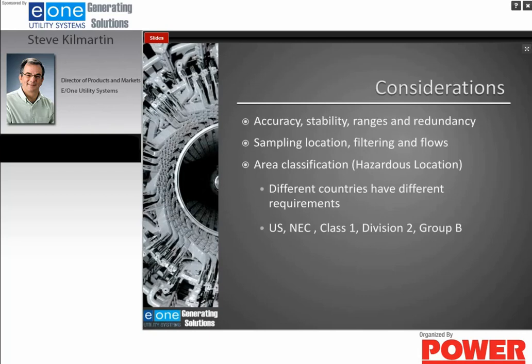Considerations when you're buying a hydrogen purity analyzer: I would say the top two are accuracy and stability, and I would put them on equal ground. All analyzers are accurate right after you calibrate them if they're calibrated properly. Not all of them are stable. So stability in my mind is as important as accuracy. When you are speccing out an analyzer, you want to make sure that it has a very low drift factor and that the unit is stable.